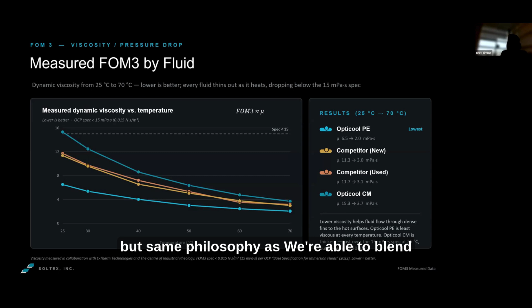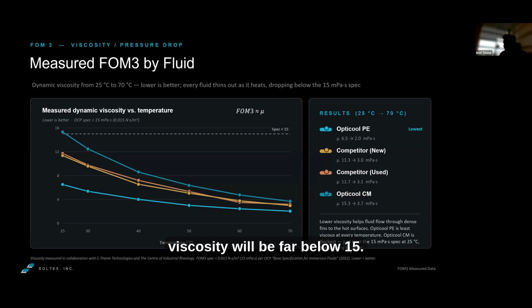For Opticool CM, you'll see that it's the thickest fluid here at 25 degrees Celsius, but same philosophy as before. We're able to blend and meet any product within the range of the two. Notably, within the operating temperature range we expect these systems to be in, Opticool CM's viscosity will be far below 15.